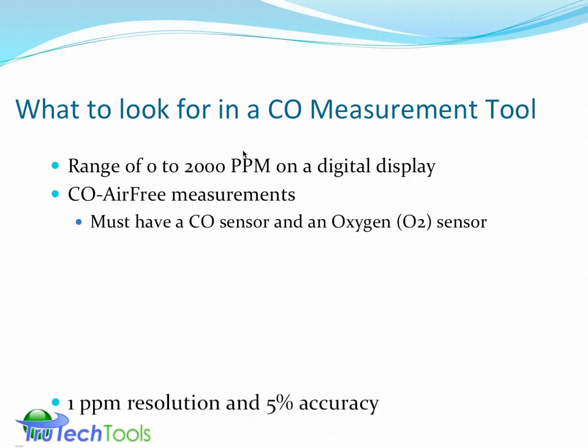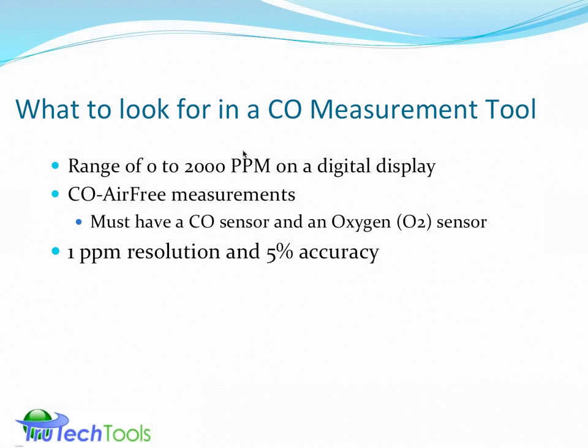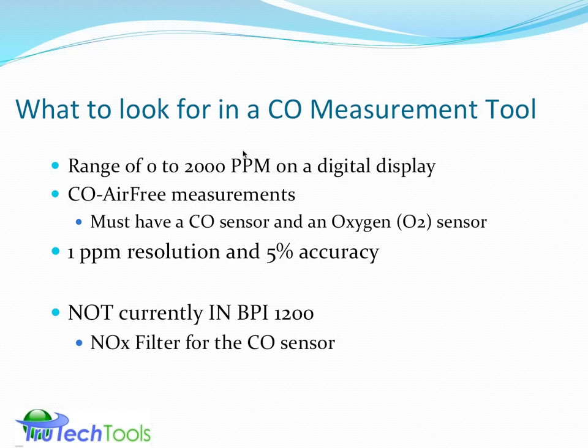Also looking for 1 ppm resolution and 5% accuracy. That's another requirement that's in the standard. And there is something that's not currently in BPI 1200, which I'm encouraging BPI to look at: I believe there should be a NOx, or nitric oxide, filter for the CO sensor. NOx usually comes from nitrogen in the air. Air is about 78 to 79% nitrogen, or nitrogen can be bound in the fuel, but mostly it's nitrogen in the air. Nitrogen and oxygen in the air can chemically combine in the combustion system to produce nitric oxide. Nitric oxide tricks a CO sensor.